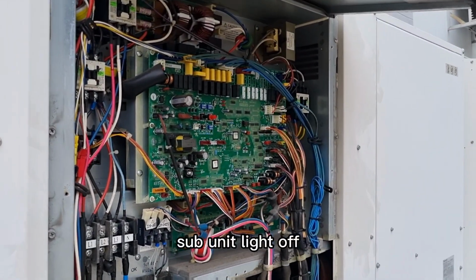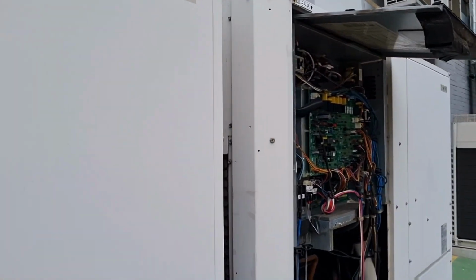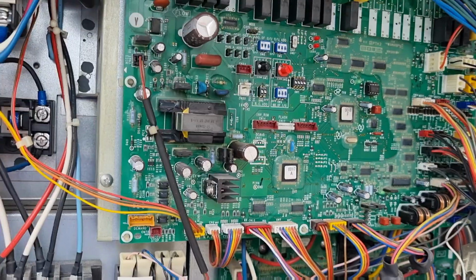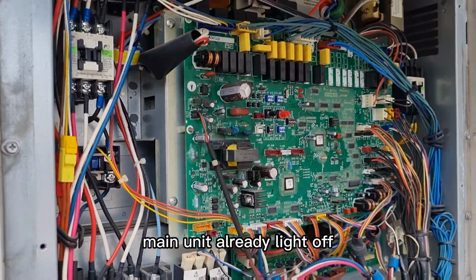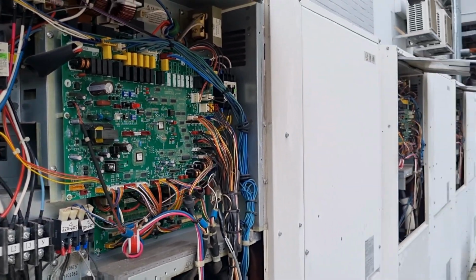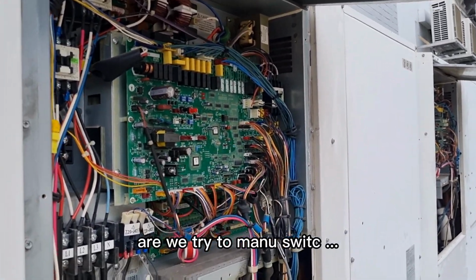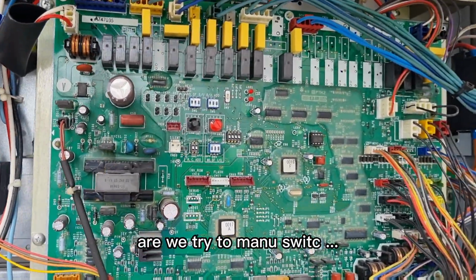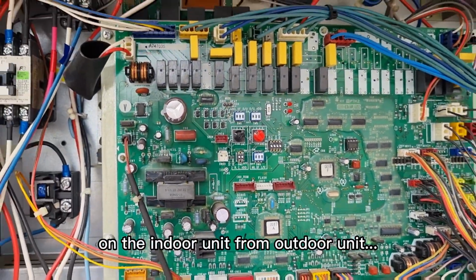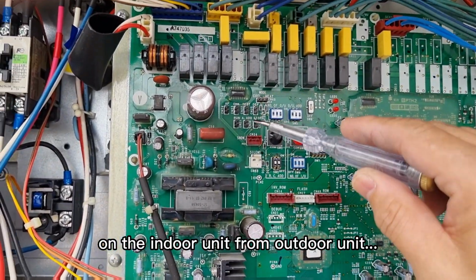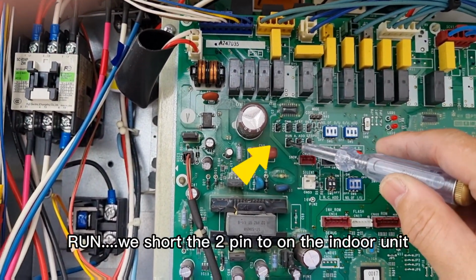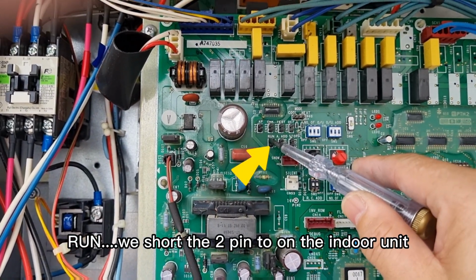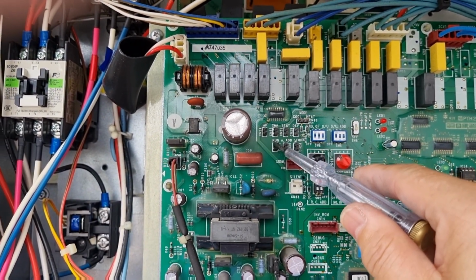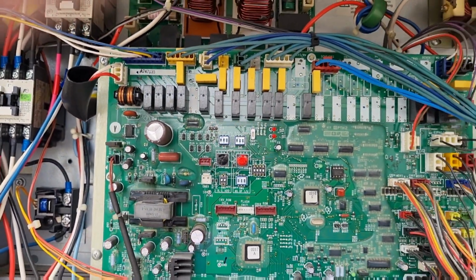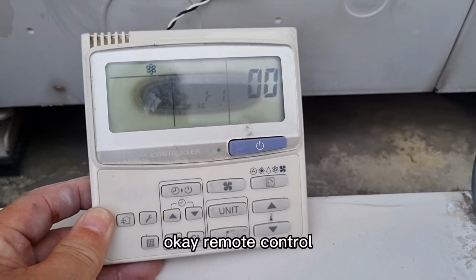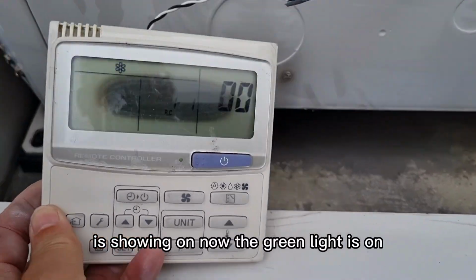Okay, subunit light off. Subunit light off. Okay, main unit light is already off. We try to manually turn on the indoor units from the outdoor unit. Okay, run. We short the two pins to turn on the indoor units. Okay, we wait for a while. Okay, remote control is showing on now. The green light is on.